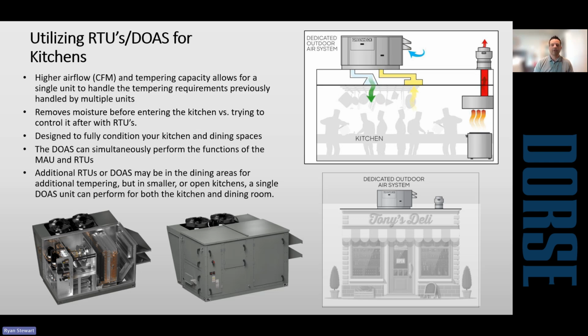When you look at that from a cost standpoint, yes, these are more expensive than a typical RTU or a makeup air unit, but you've eliminated the 2 duct runs, the 2 roof penetrations, and the electrical associated with it. Big picture, you get pretty close, and there are some really good benefits from a comfort standpoint and efficiency.